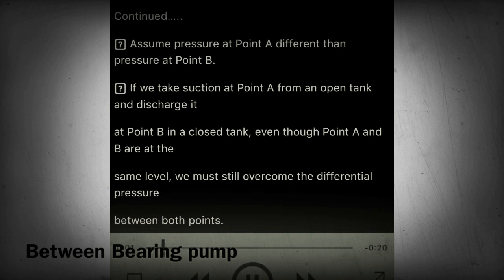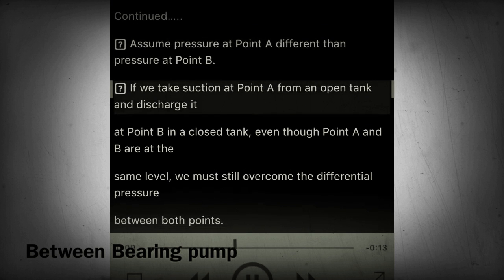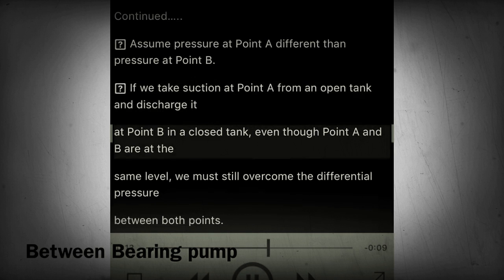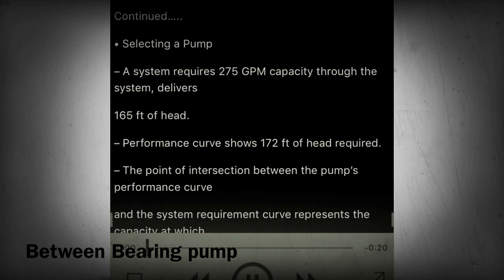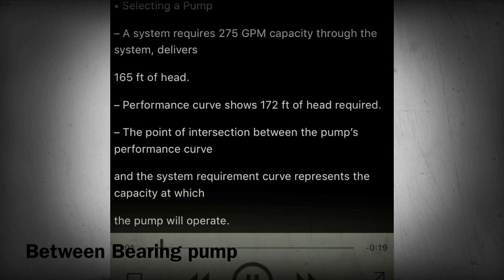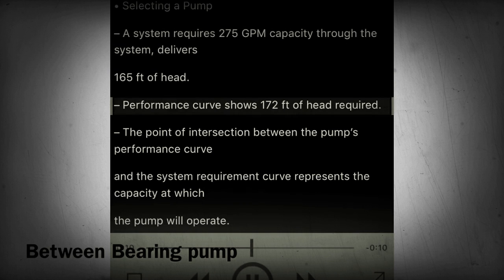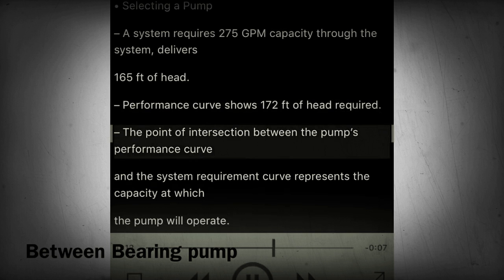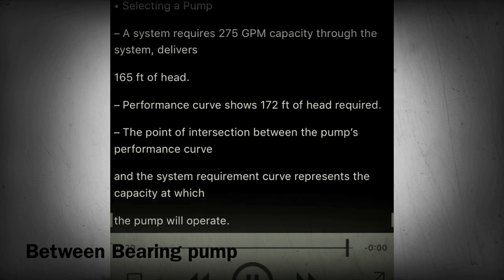Sections 33-34 - If the pressure at point A is different than the pressure at point B — for example, taking suction at point A from an open tank and discharging at point B into a closed tank — even though points A and B are at the same level, we must still overcome the differential pressure between both points. For pump selection example: a system requires 275 GPM capacity, delivering 165 feet of head, while the performance curve shows 172 feet of head required. The intersection of the pump's performance curve and the system requirement curve represents the capacity at which the pump will operate.